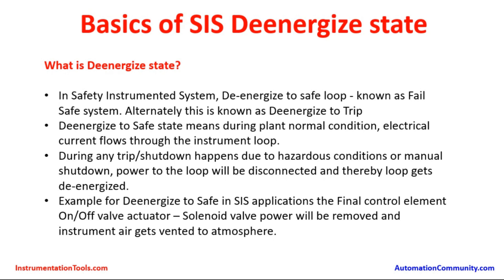De-energized to safe state means that during normal plant conditions, electrical current flows through the instrument loop. When plants are in normal operating conditions, valves in the safety instrumented system — specifically valves that are isolating a process, equipment, or a vessel — will be in the open position using the solenoid valve.